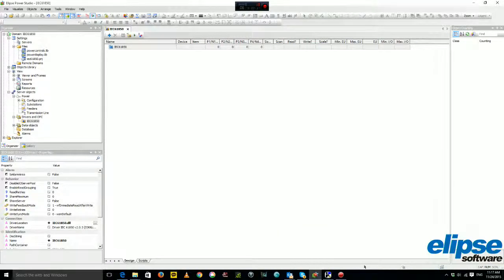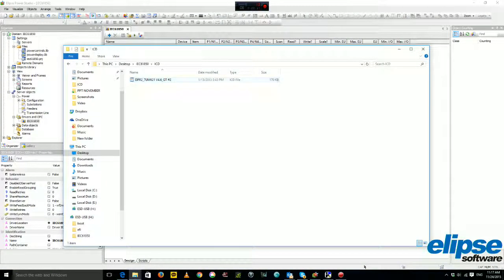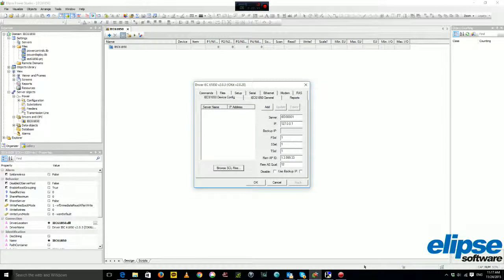And the other one is one ICD file from a Siemens relay. So I have to input this IED information into my driver setting. Here I can add 25 IEDs in this client. I can type the information manually or I can import the ICD file directly.